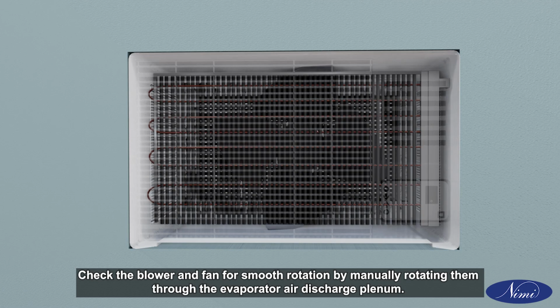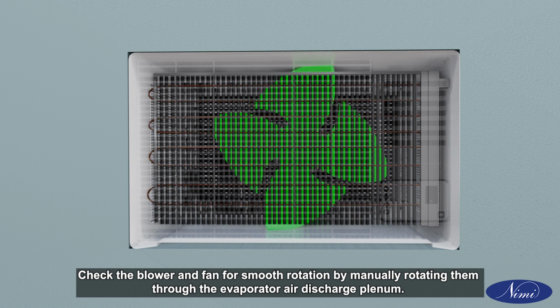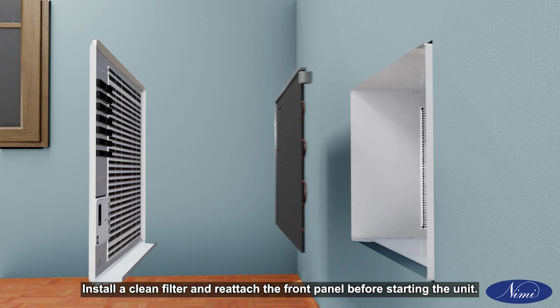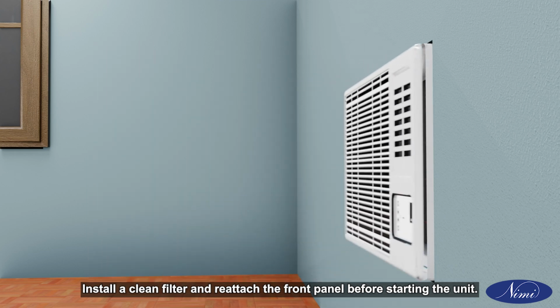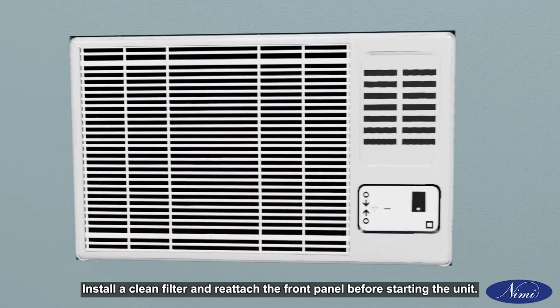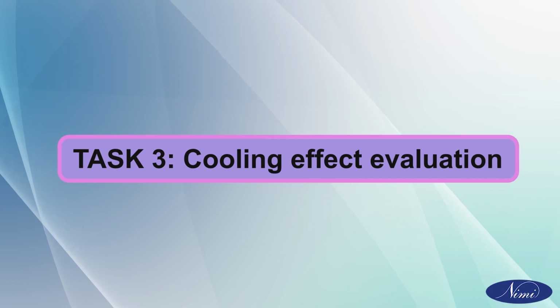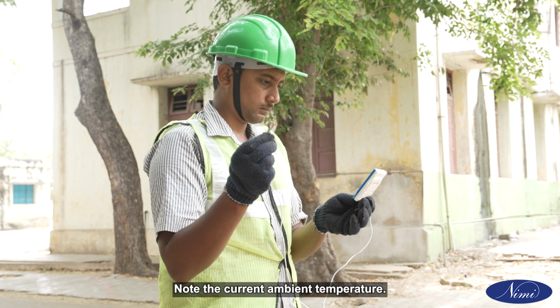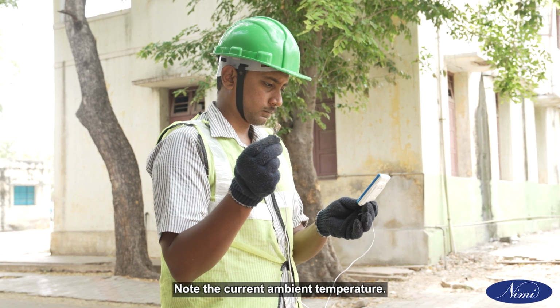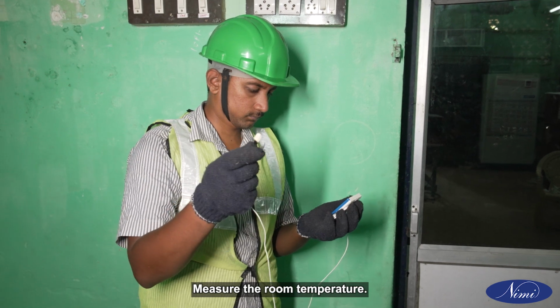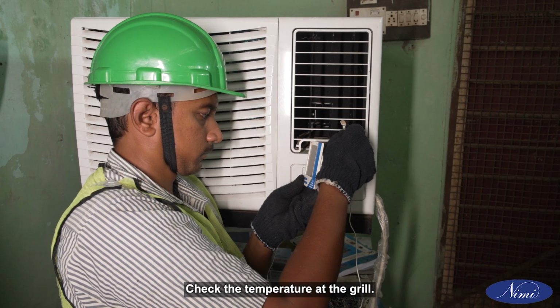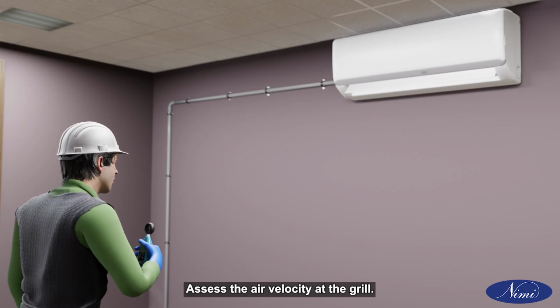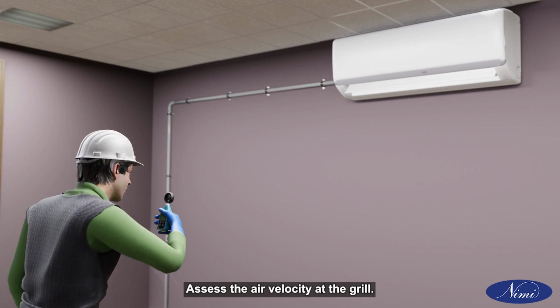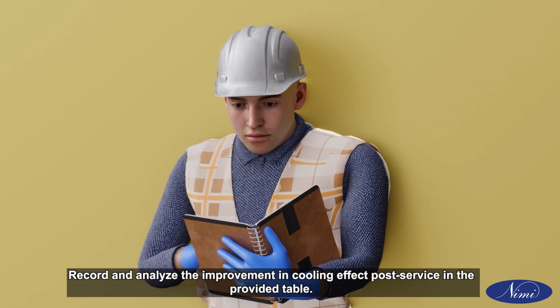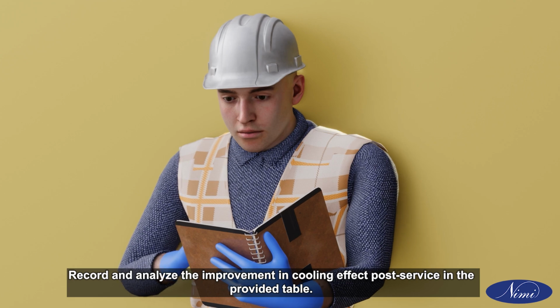Check the blower and fan for smooth rotation by manually rotating them through the evaporator air discharge plenum. Install a clean filter and reattach the front panel before starting the unit. Task 3. Cooling effect evaluation. Note the current ambient temperature. Measure the room temperature. Check the temperature at the grill. Assess the air velocity at the grill. Record and analyze the improvement in cooling effect post-service in the provided table.